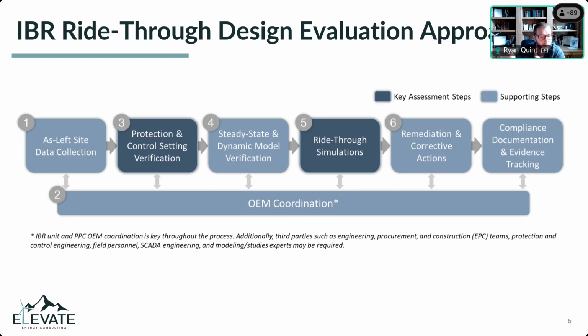Step 5 is we run a set of crafted simulations testing the requirements and sub-requirements of the standard in specific ways - focused on permissive region, mandatory region, continuous region, reactive power contribution, momentary cessation, and other sub-requirements, making sure that things which can't be captured with step 3 efforts, the protection and control verification, are evaluated with dynamic ride-through simulations.